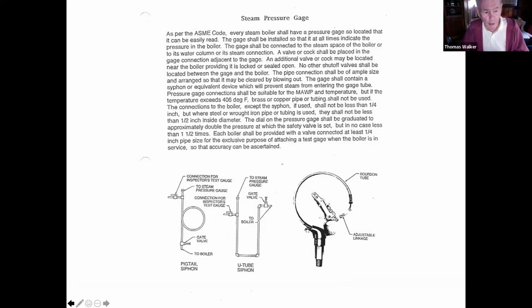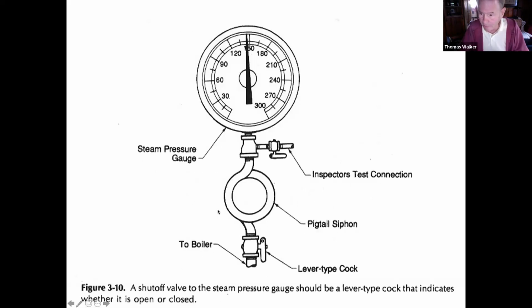They'll ask you, when do you need a pigtail siphon? It's anytime the pressure gauge is used on steam. The high temperature of steam will damage the Bourdon tube.